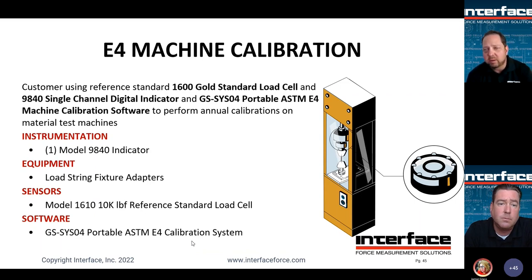So we'd use a 9840, again, portable, dual channel. It would be single channel in this case. They also come in dual channel, very portable, very accurate instrument, very common, very popular. You'd have necessary load string adapters. It would be a function of the threading or fixturing that is already there in the frame. And of course, you'd use another 1600 series reference standard as the way to go. And the GS-SYS04 calibration system also includes E4 specific software. So you'll have a E4 compatible calibration certificate report that comes from that.